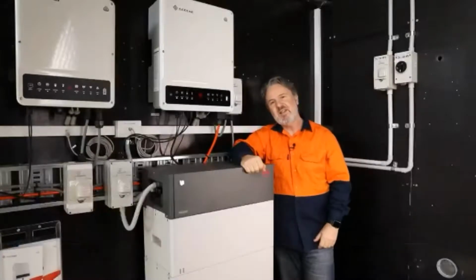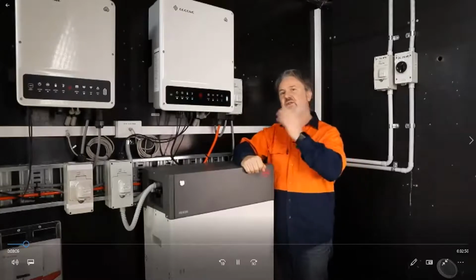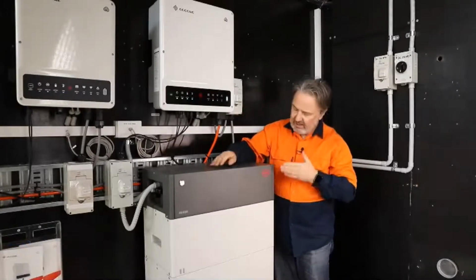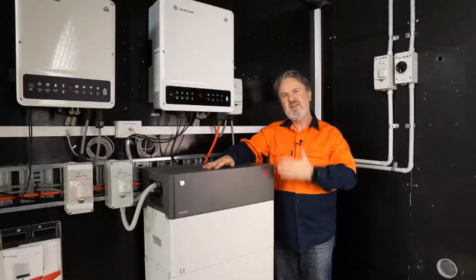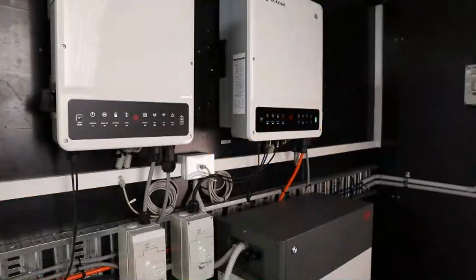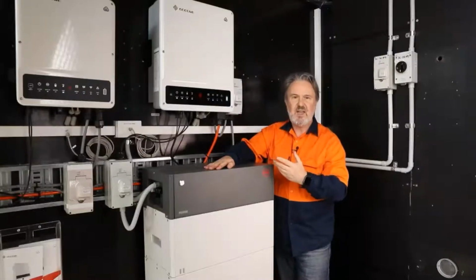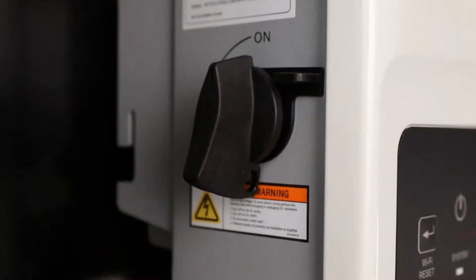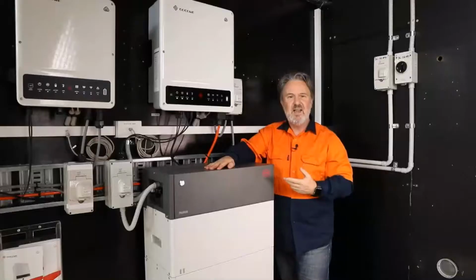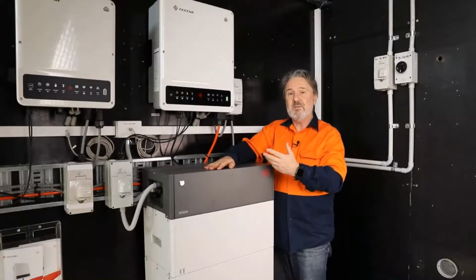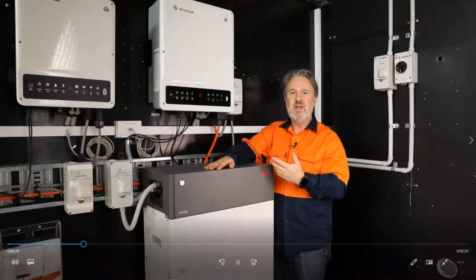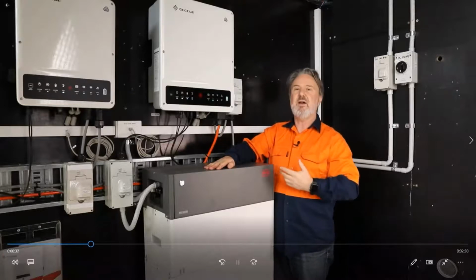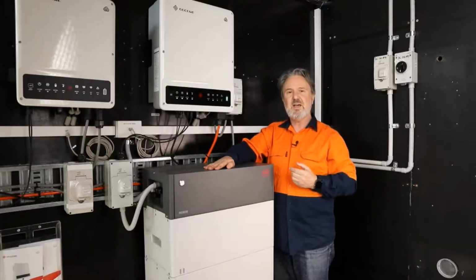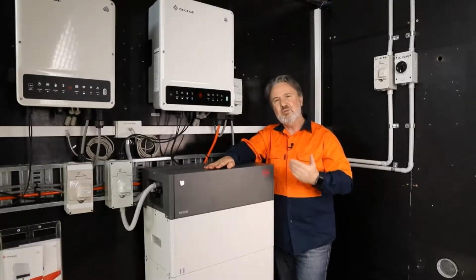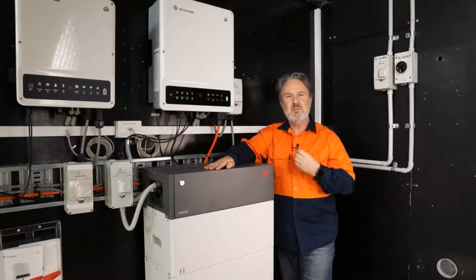Morris from the Smart Energy Lab, and today in the lab we're looking at the new GoodWe EH and ET hybrid inverters and the BYD HVM battery. These are an amazing combo. The single phase EH inverter has some amazing features - it's got a built-in DC isolator, which is fabulous, so you don't have to add an external DC isolator. It's upgradable from a pure grid connect system to a UPS system with an activation code, and it also has very high power overrating. This unit can be powered at 33% more PV power than the AC output, which is great because on less than perfect days, you really want that extra PV watts to maximize the amount of renewable energy you're using.